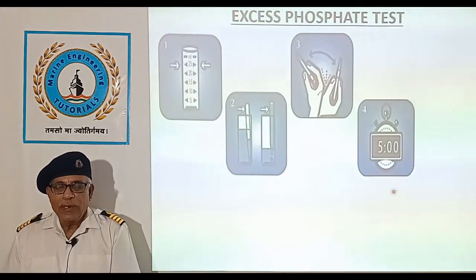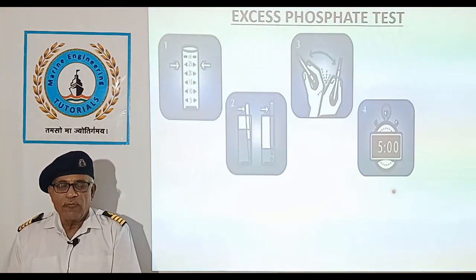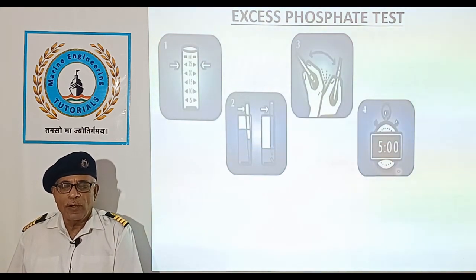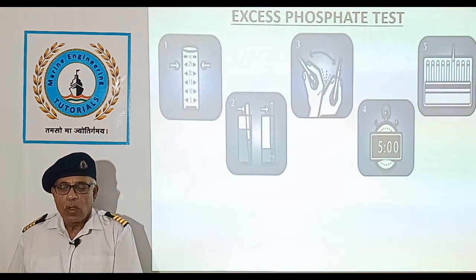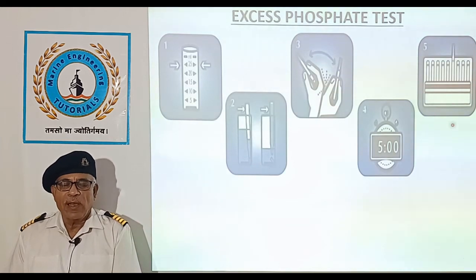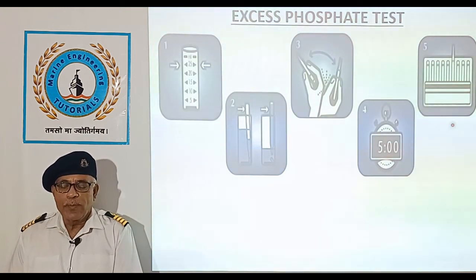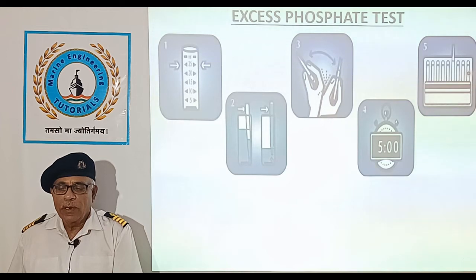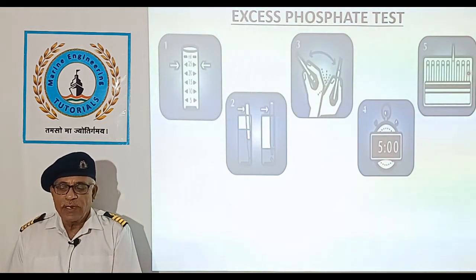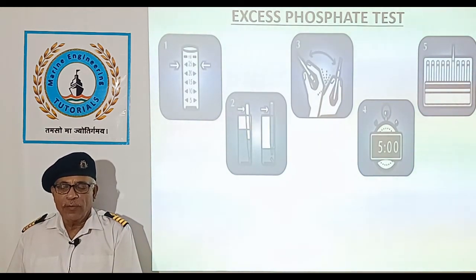Mix the contents of the ampoule by inverting it several times, allowing the bubble to travel from end to end each time. Wipe all liquid from the exterior of the ampoule and wait for 5 minutes for full color development. While using the comparator, ensure it is illuminated by a white light directly above it. The filled boiler phosphate ampoule should be placed between the color standards for viewing. It is important that the ampoule be compared by placing it on both sides of the standard tube before concluding that it is darker, lighter, or equal to the standard.